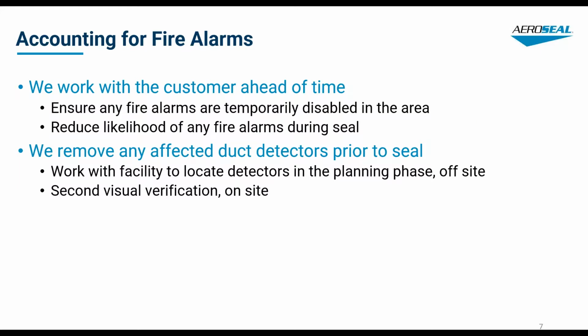Accounting for fire alarms. This is another thing that we'll do in the process of talking to the customer before we actually mobilize to the project. With Aeroseal, during the sealing period, we need the fire alarms to be in test, because there may be fogging issues, which could set off the fire alarm or a duct detector. So we'll work with the customer beforehand and say, hey, we're going to be sealing this area on this date, and we're going to need the fire alarms shut down and disabled between this time frame.